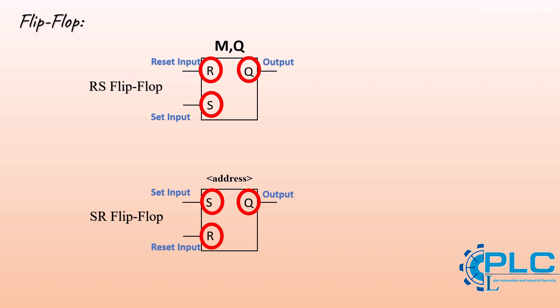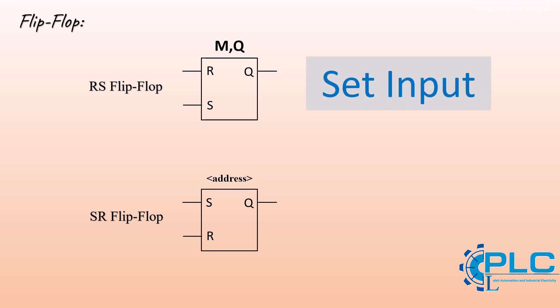In these flip-flops, when the set S input is activated, the assigned address and the flip-flop's output becomes active and stays active until the reset R input is triggered. The SR flip-flop works similarly to the RS flip-flop, but with one key difference. In an RS flip-flop, the set S input has priority over the reset R input. But in an SR flip-flop, the reset R input has priority over the set S input.